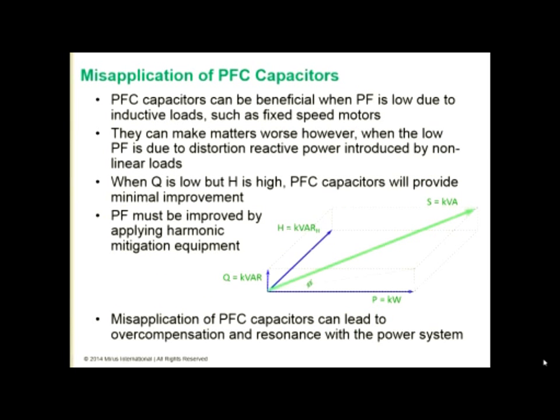But we have misapplications of power factor correction capacitors. PFC capacitors can be beneficial when power factor is low due to inductive loads, such as fixed speed motors, but they can make matters worse when the low power factor is due to distortion reactive power introduced by nonlinear loads. So when Q is low but H is high, PFC capacitors will provide minimal improvement. Power factor must be improved by applying harmonic mitigation equipment.